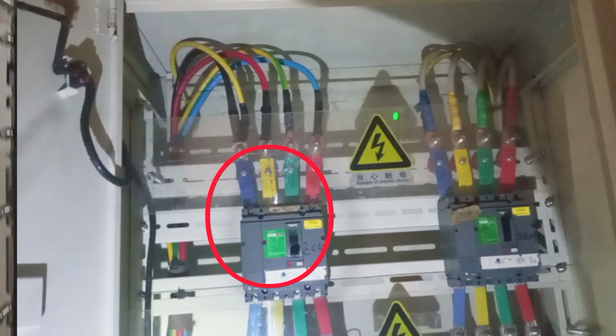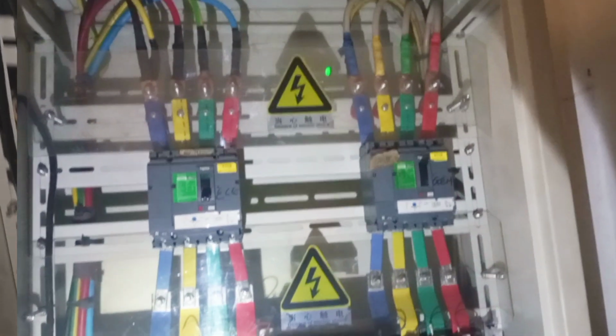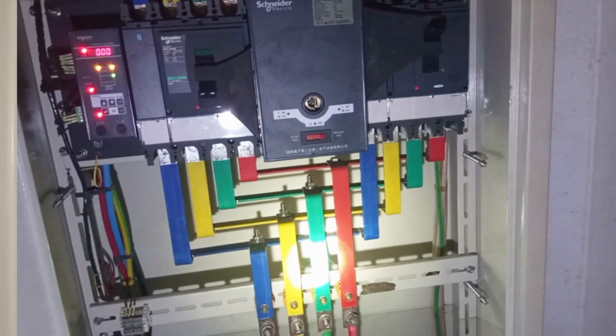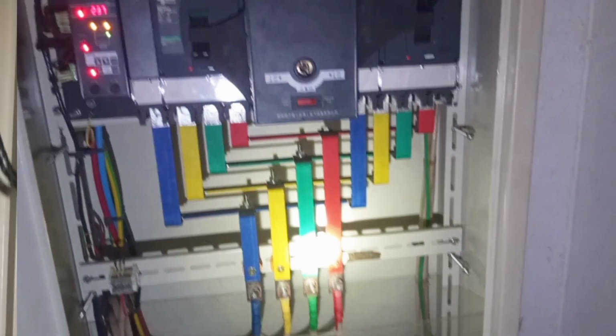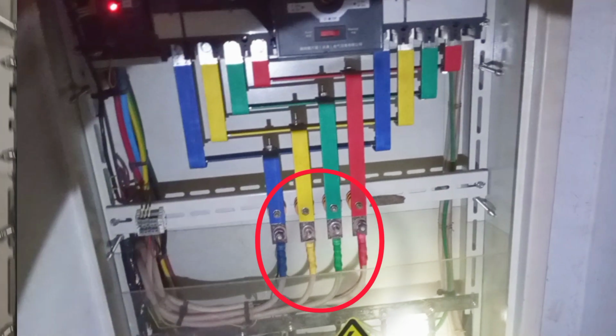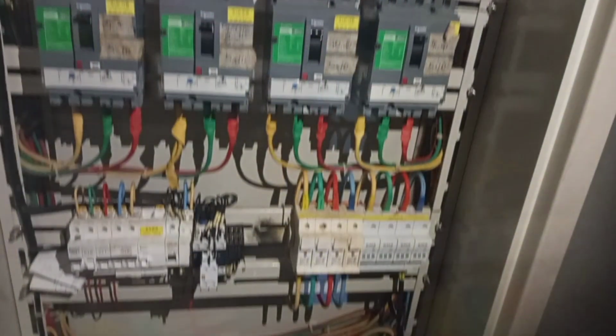So we have one side that connects to the grid power, and then we also have the other side that connects from the generator. So we have two supply points connecting to the changeover switch, and these two power supplies have a common output point that goes to supply power to the building. Okay, so here as you can see at the output we have the two power supplies coming together. So at any point in time, one of the sources will give us supply to this building, either from the grid or from the genset. So depending on the power requirements of the building, you have to size your changeover switch appropriately.